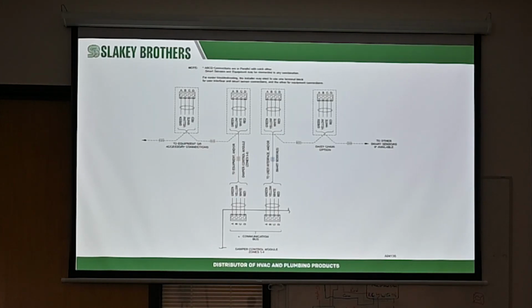Your wiring for your zone board. So on your zone board, you got 2 terminals of the ABCD. In order to help when you do have a problem with a communication fault or something's not working right, if you can do it this way, this is perfect on a brand new house, because everything's all open. You can run wires very easily. But if it's a replacement of a non-evolution system that was zoned, it's kind of hard to rerun all those thermostats, especially if it's upstairs, downstairs, and so on.